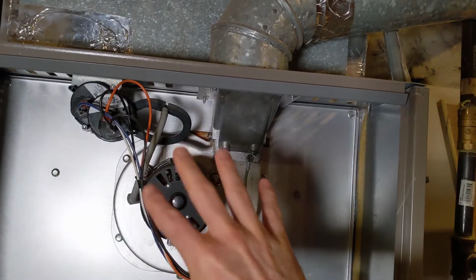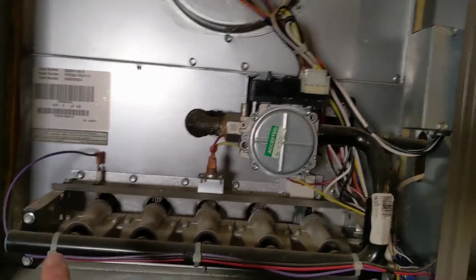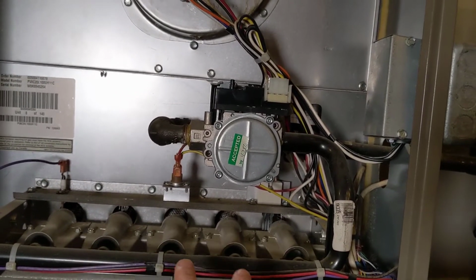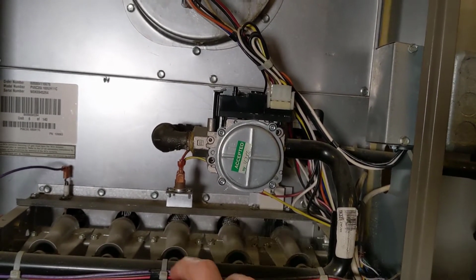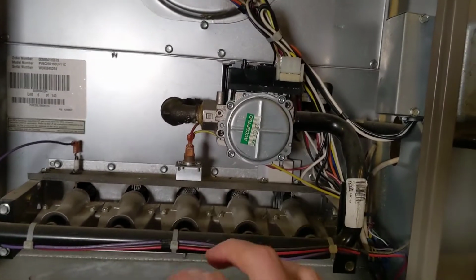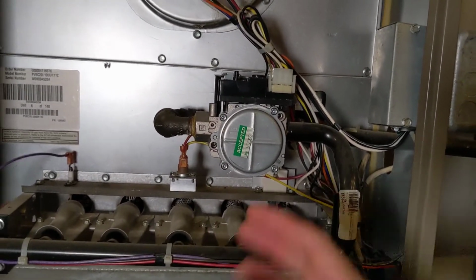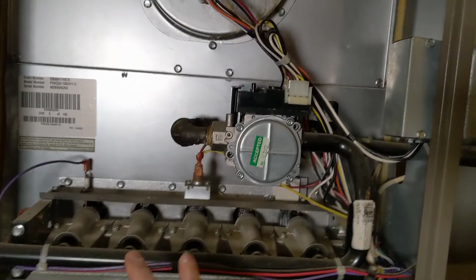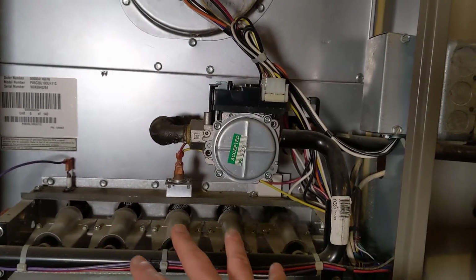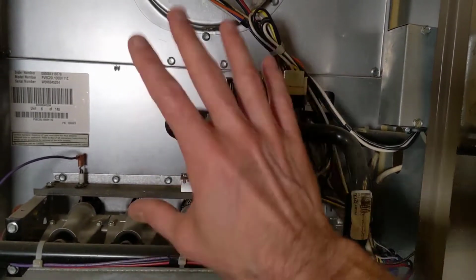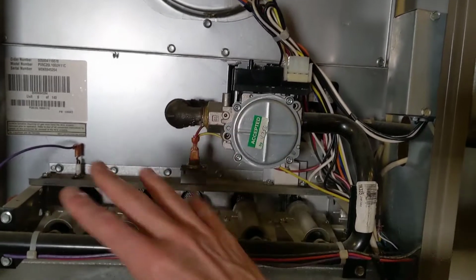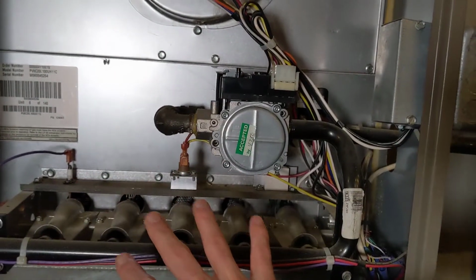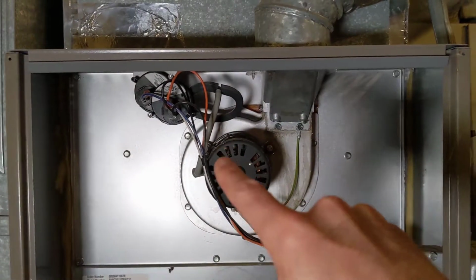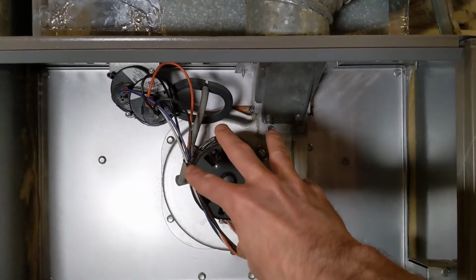The purpose of this is to provide draft to our burners so that when these things fire up, it licks the flames like a jet into the heat exchanger. Without this draft motor, what would happen is it would look like an outdoor gas stove, where this box would just be on fire, and that would not be helpful, nor would it be safe. So the first thing that should happen is this motor should start up.